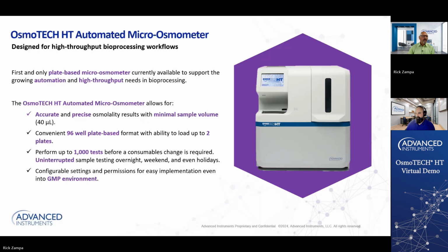Right. So this is the OsmoTECH HT. We're going to get into this in a little bit more detail here in a few minutes. It's the only plate-based micro-osmometer available in the marketplace. So we use a 96-well microtiter plate to introduce the samples into the instrument. The minimum sample volume is 40 microliters, and it can perform up to 1,000 tests before requiring a change in the consumables. And you can configure the settings for any part of your process, whether it's a GMP environment or all the way down to your research organizations where you may not need as strict requirements for your data logging or your data management or your compliance.